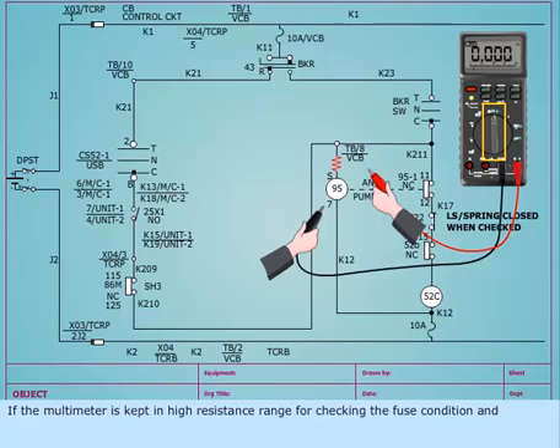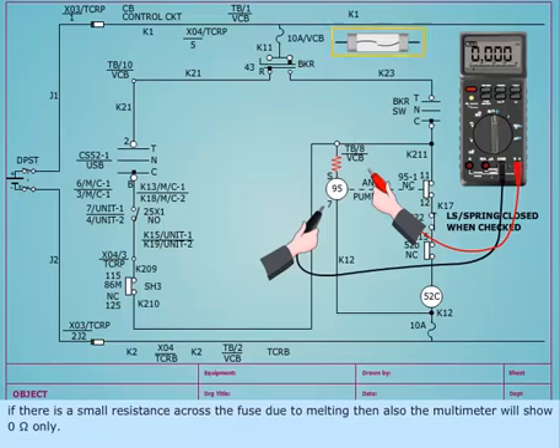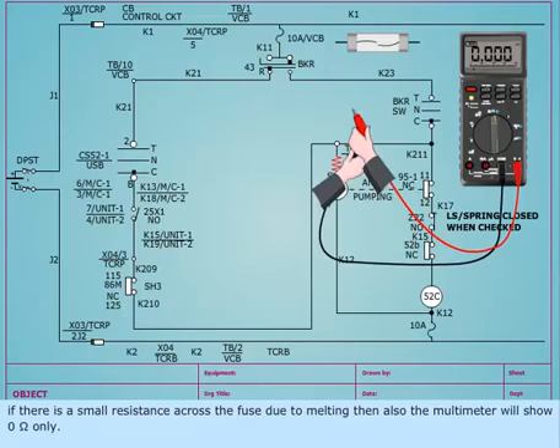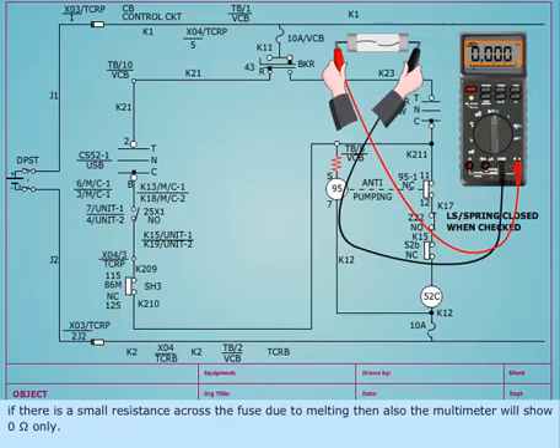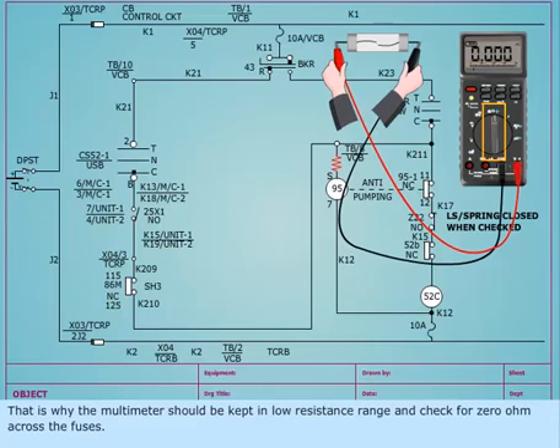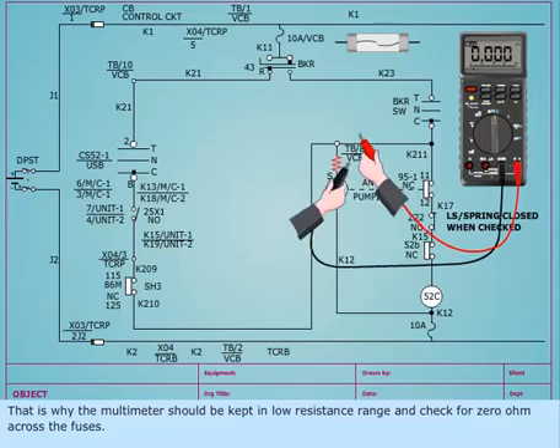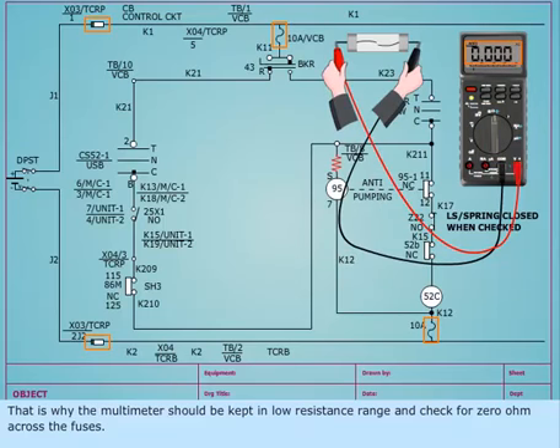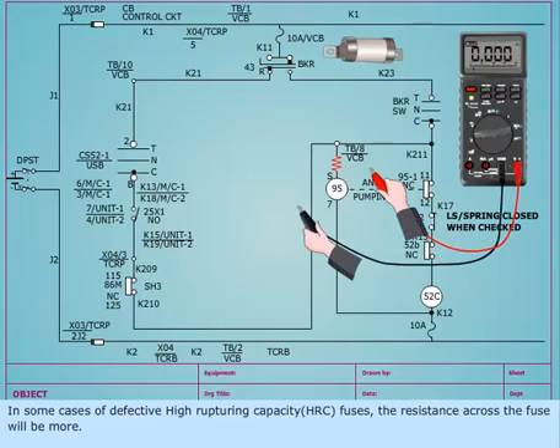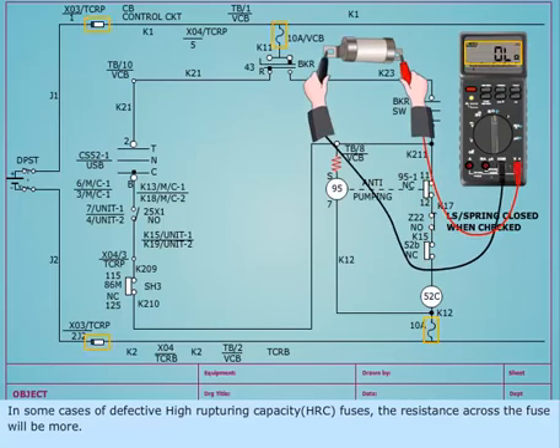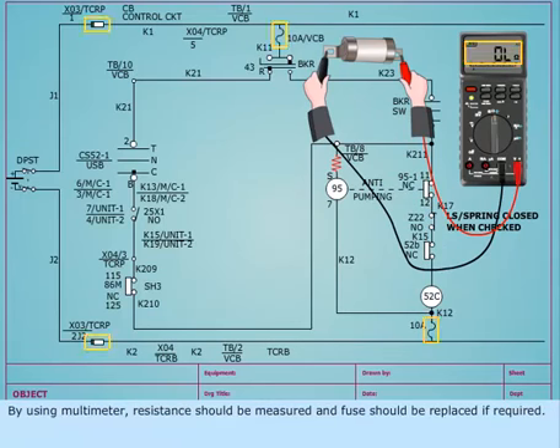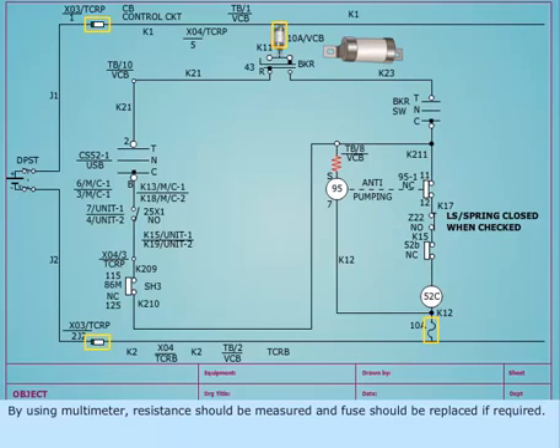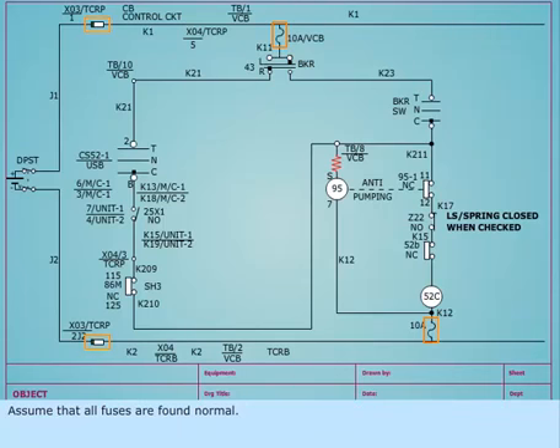If the multimeter is kept in high resistance range for checking the fuse condition, and if there is small resistance across the fuse due to melting, then also the multimeter will show 0 ohm only. That is why the multimeter should be kept in low resistance range and check for 0 ohm across the fuses. In some cases of defective high rupturing capacity HRC fuses, the resistance across the fuse will be more. By using multimeter, resistance should be measured and fuse should be replaced if required. Assume that all fuses are found normal.